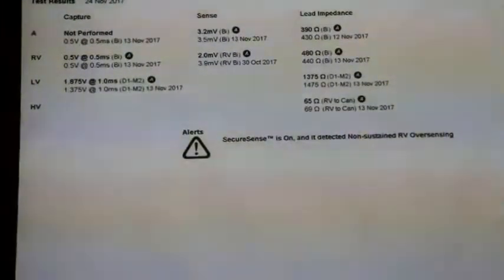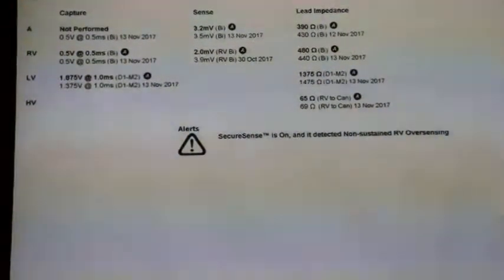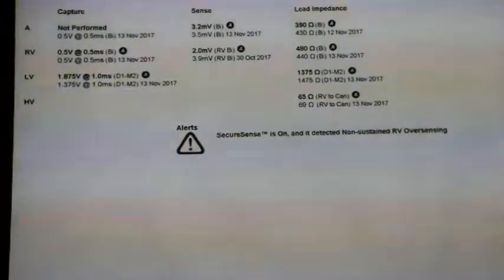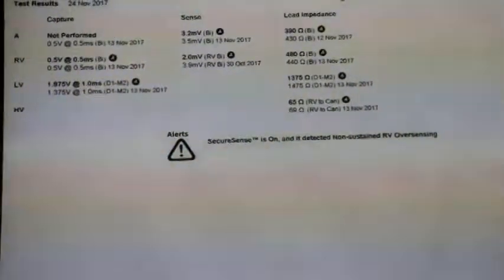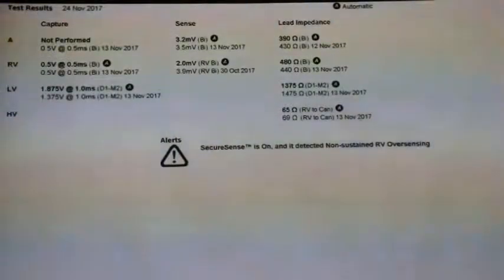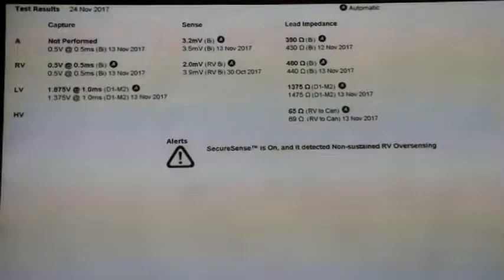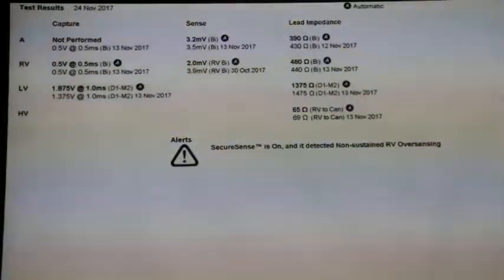You said something that's a little counterintuitive to me. You said the ventricular lead had a high impedance, which meant it's going to take a little less current. Yes, from Ohm's equation. But when we see high impedance, we usually get a feeling that there's something wrong. What is the definition of high impedance? More than 2000? This is less than 2000. This is okay. This is good. If we get numbers like that, I'm like, yeah, brilliant. There's nothing wrong with the lead. It's a new lead.